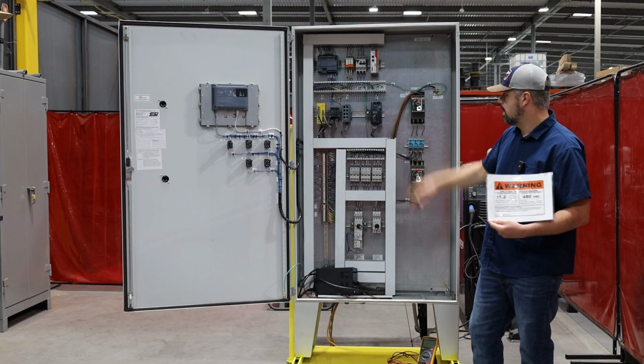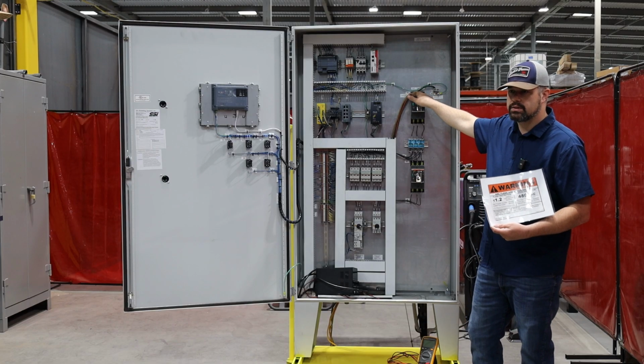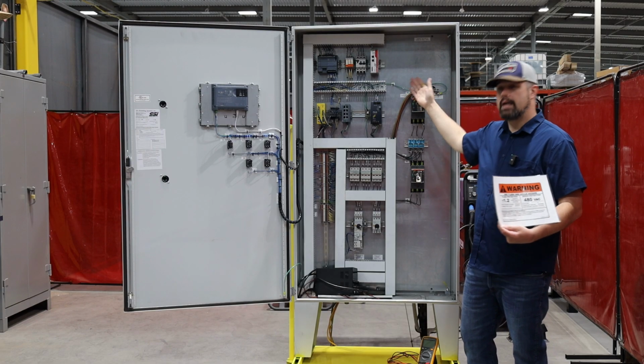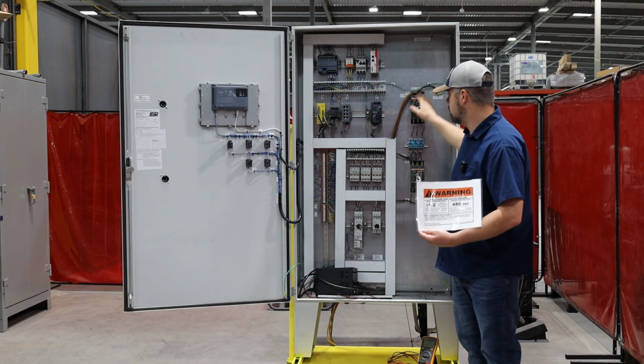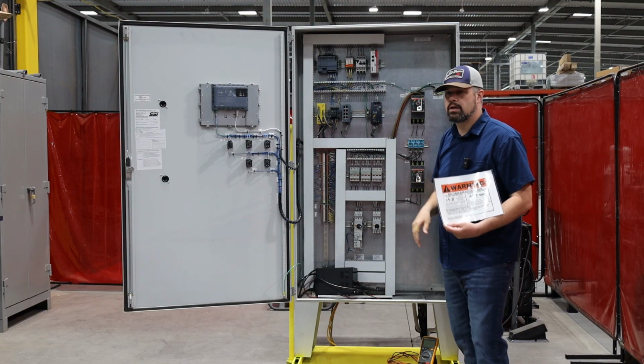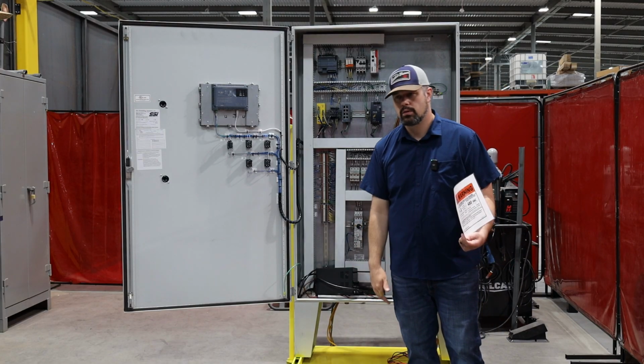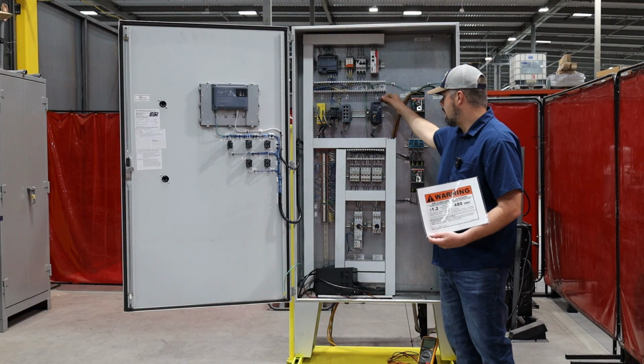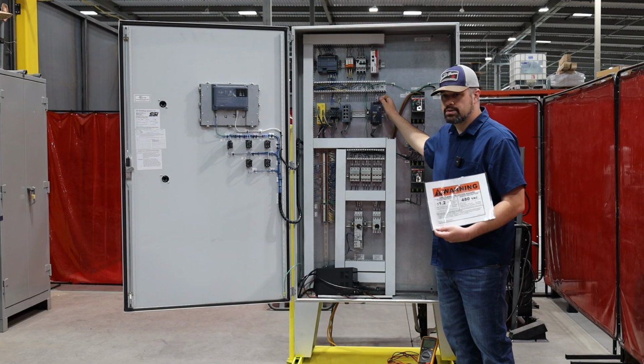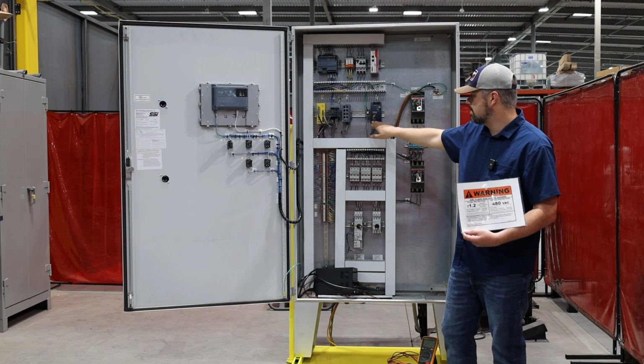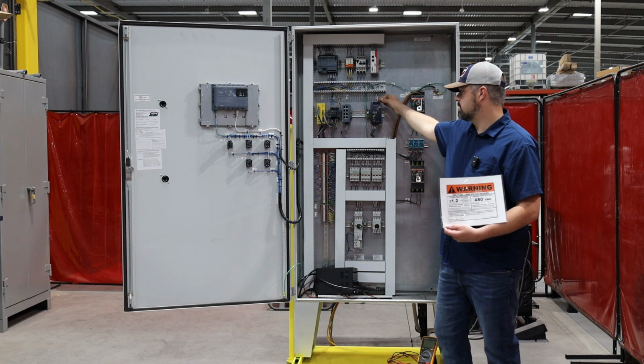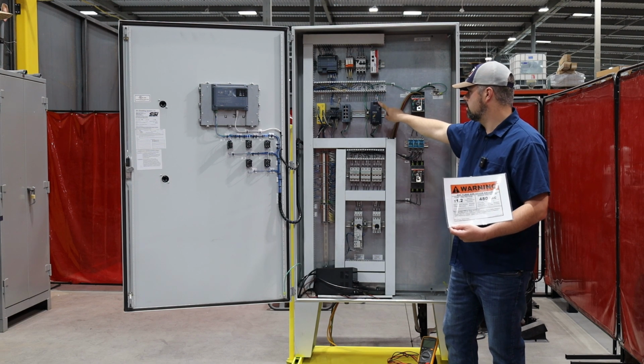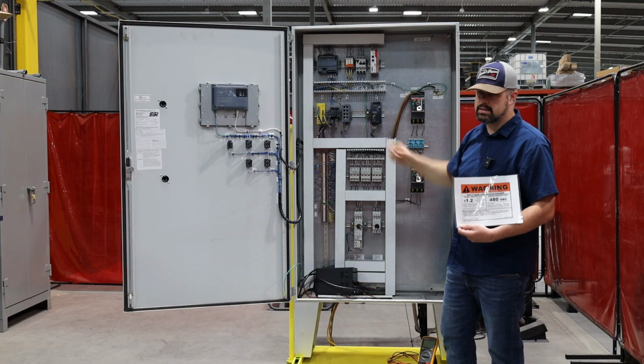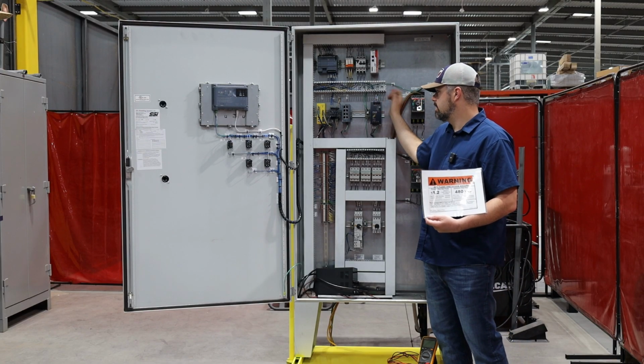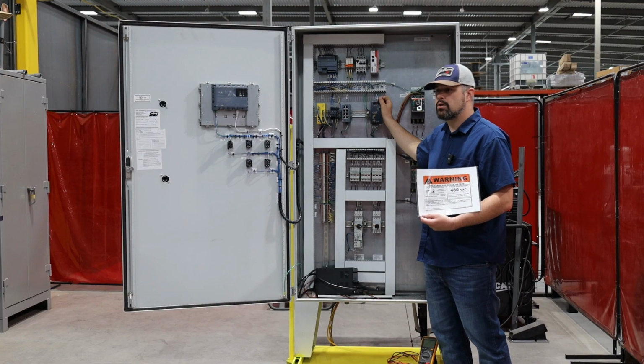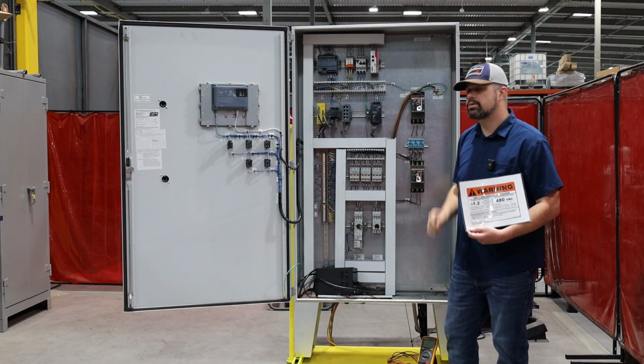So what does that tell you? Well, everything on this label applies to that voltage that's present there, right? So you've got to respect an 18-inch boundary. You can't do anything within 18 inches of this exposed electrical conductor because that would be considered live electrical work, right? So if you had a wire that came out on this power supply, and this takes 480 and drops it down to 24 volt DC, and you just had a simple little wire that came out, well, this is clearly within 18 inches of this. There you go. You cannot take your screwdriver and use it on this terminal to reseat that wire. That's electrical work, and you're within 18 inches, okay? So those are the types of things.